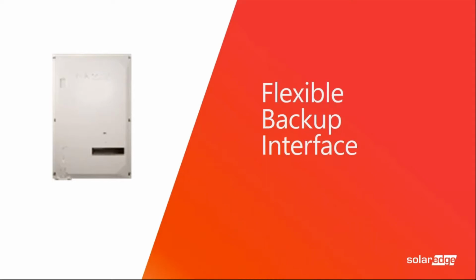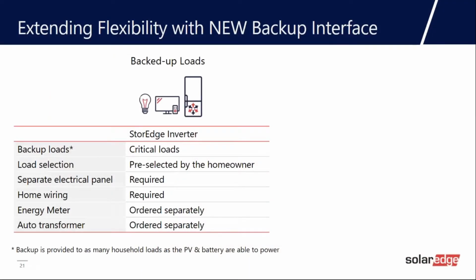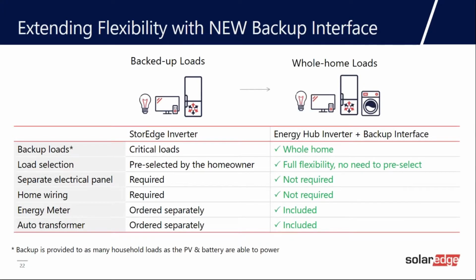All right, so flexible backup interface. Let's talk about the backup interface. Again, this is my brain candy, so I'm really proud of it. When we talked about backup before, we had our SolarEdge inverter, and we had to launch the StorEdge inverter, and the transfer switch was located inside the DC disconnect. So you only got 21 amps of backup capability, and by routing everything through the inverter, it was ingenious in that it was easy to install, but that means we could only do small loads. We couldn't do a lot of big loads for backup.